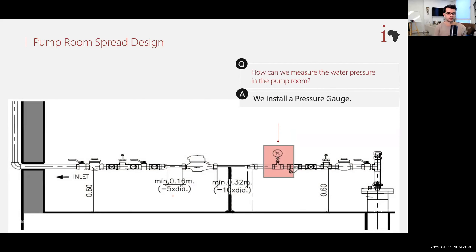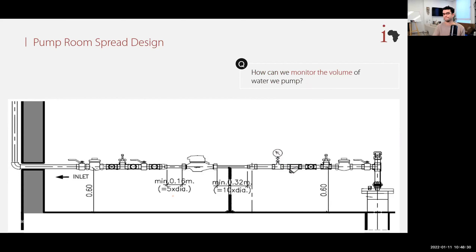It's very important to know the pressure in the pump room — to check if pipes have leaks, if the pump is working properly, or if the filter needs cleaning. We install a pressure gauge, which tells us the current pressure in the system. Its units are usually kilopascal or bar — one bar equals 100 kilopascal. Importantly, the pressure gauge must come after the screen filter, because it can get damaged by debris from the borehole.